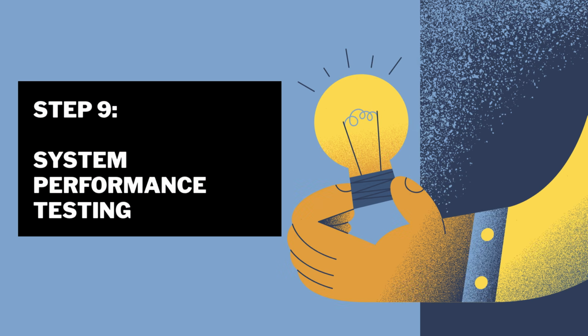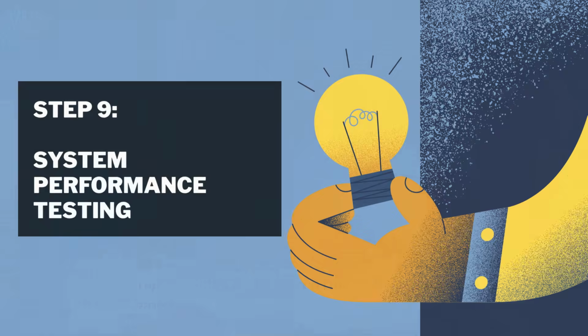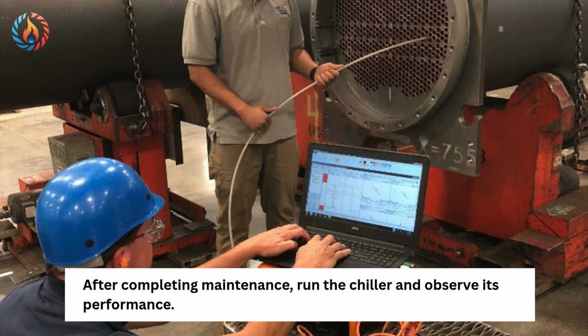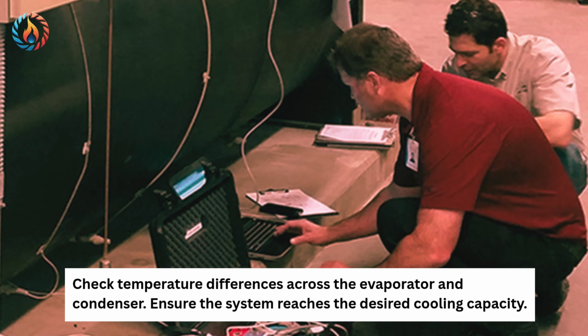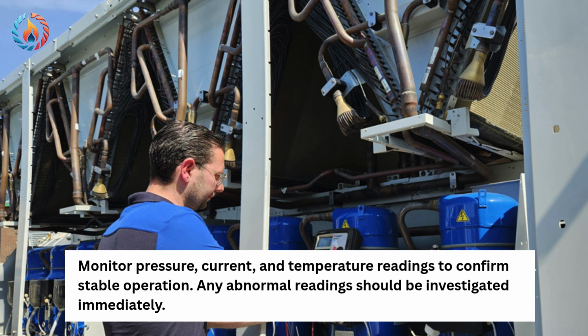Step 9. System performance testing. After completing maintenance, run the chiller and observe its performance. Check temperature differences across the evaporator and condenser. Ensure the system reaches the desired cooling capacity. Monitor pressure, current, and temperature readings to confirm stable operation. Any abnormal readings should be investigated immediately.